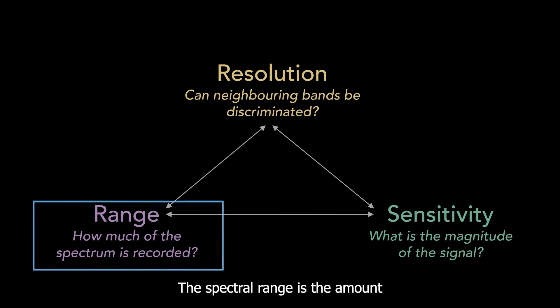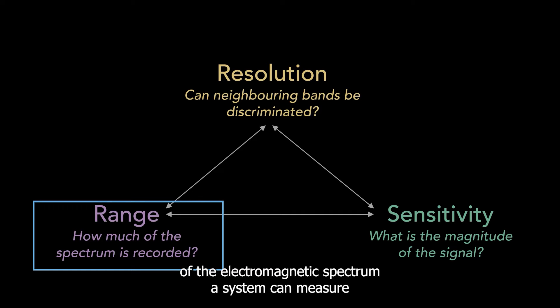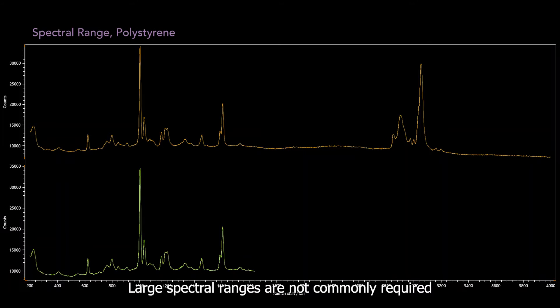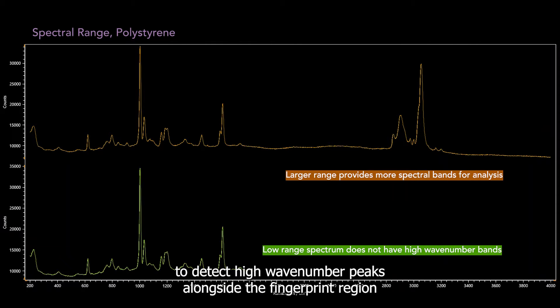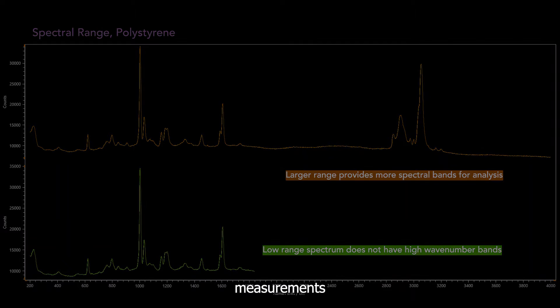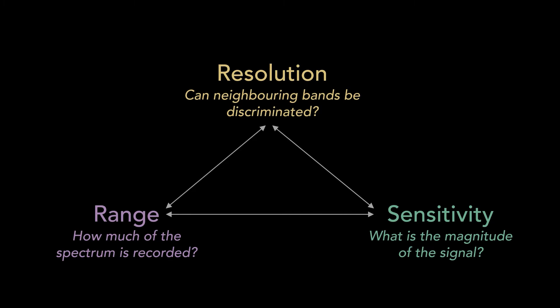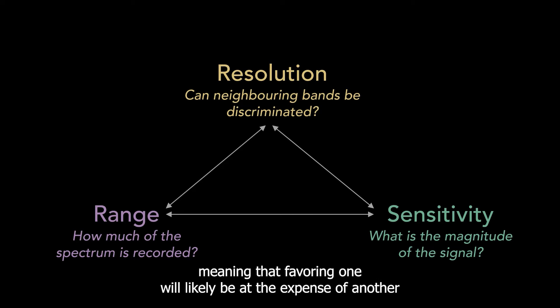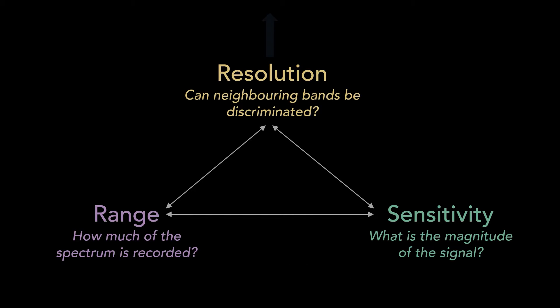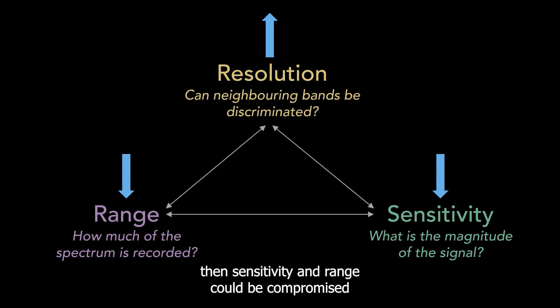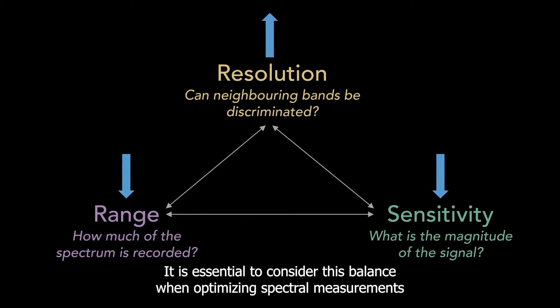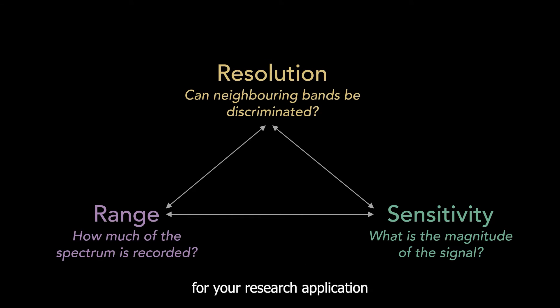The spectral range is the amount of the electromagnetic spectrum a system can measure. Large spectral ranges are not commonly required. However, a more extensive range can be advantageous when a user wishes to detect high wavenumber Raman peaks alongside the fingerprint region, or even configure a system for photoluminescence measurements. These three parameters are always in balance, meaning that favouring one will likely be at the expense of another. For example, if a user wishes to optimize resolution, then sensitivity and range could be compromised. It is essential to consider this balance when optimizing spectral measurements for your research application.